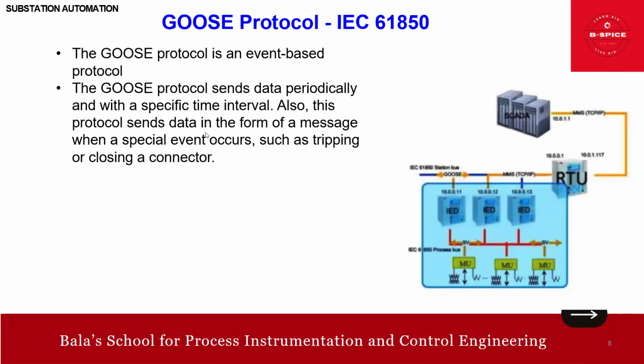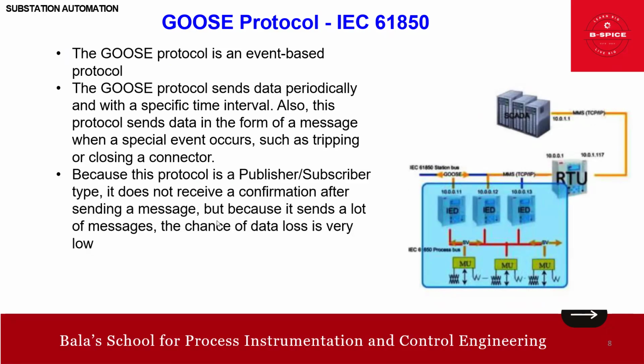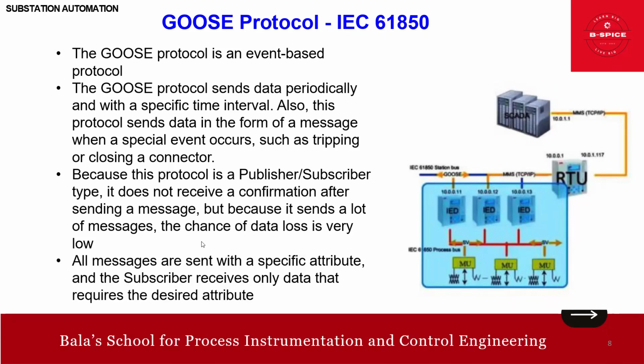Now, the GOOSE protocol is event-based, and periodic with a specific time interval. This protocol sends data in the form of a message when a special event occurs, such as tripping or closing a connector. Because this protocol is a publisher-subscriber type, it does not receive a confirmation after sending a message. But because it sends a lot of messages, the chance of data loss is very low.